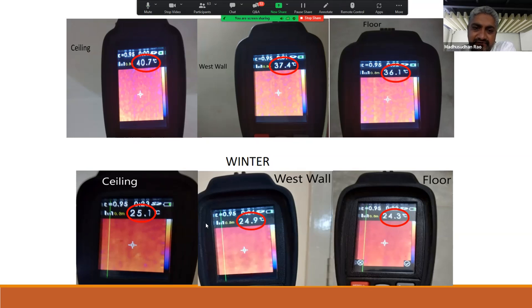Whereas in winter, in the afternoon, the same surfaces are at lower temperature. So what if we are comfortable with just fan and maybe natural ventilation when it is in this condition? If you are able to flush the heat and bring these surfaces closer to these temperatures, then we will experience comfort without requiring air conditioning. So that's the premise, right? So how do we do that?